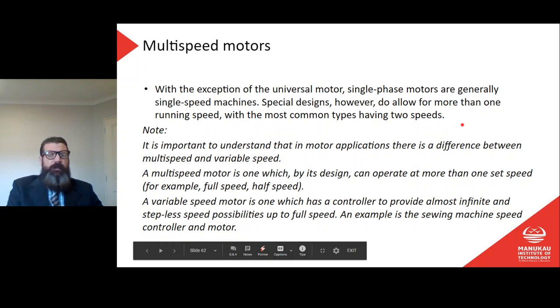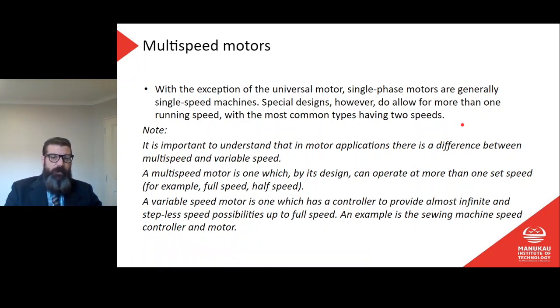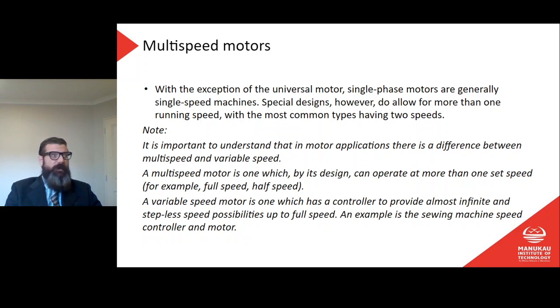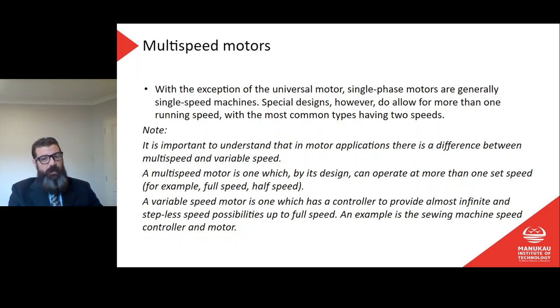Multi-speed motors: with the exception of the universal motor, single phase motors are generally single speed machines. Special designs, however, allow for more than one running speed, with the most common types having two speeds. It's important to understand the difference between multi-speed and variable speed. A multi-speed motor operates at more than one set speed by design — for example, full speed or half speed. A variable speed motor uses a controller to provide almost infinite, stepless speed possibilities up to full speed, like the sewing machine speed controller motor discussed earlier.